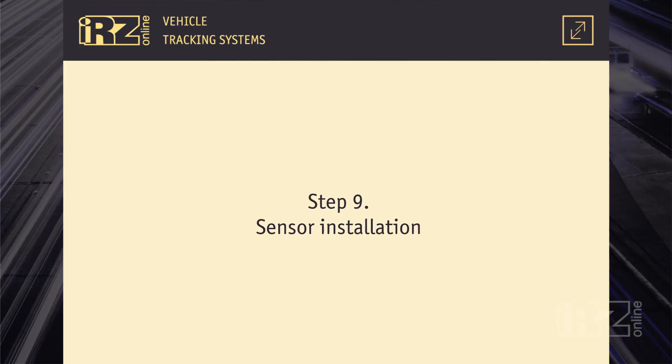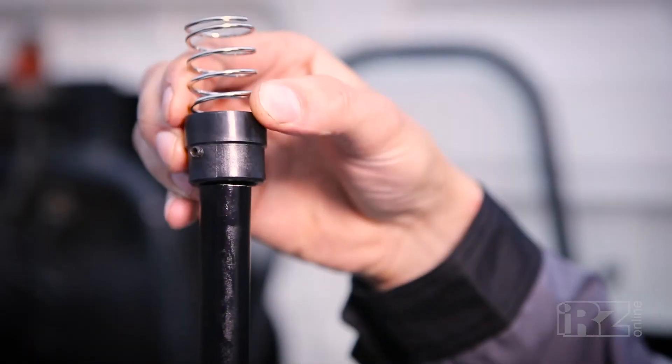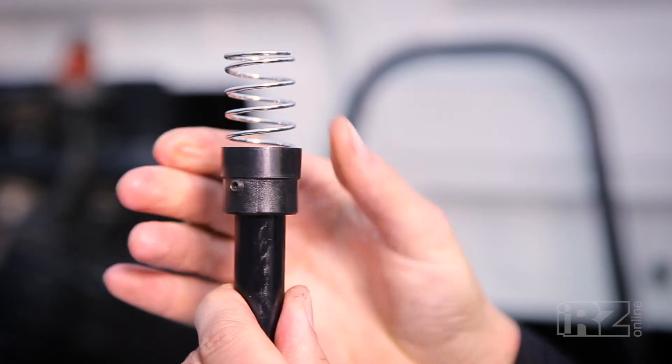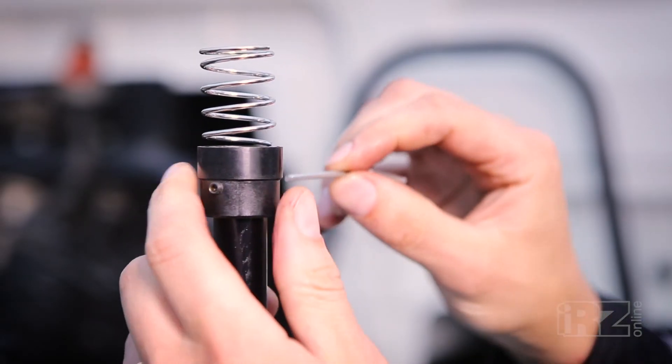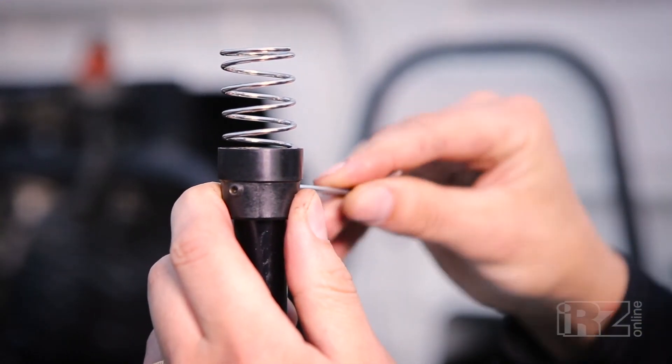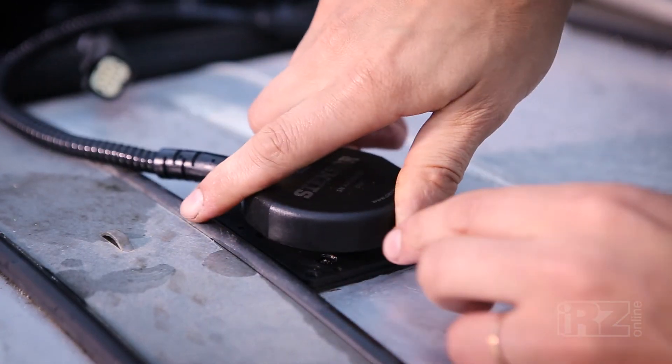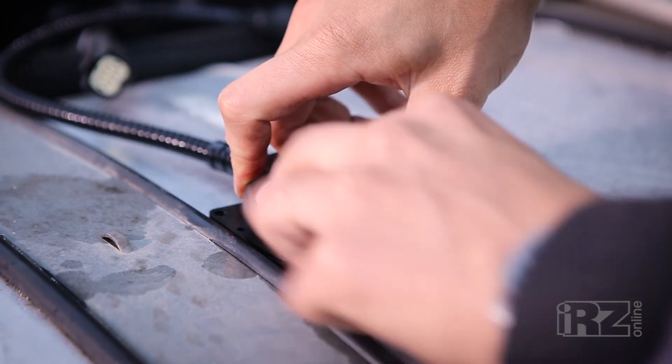Carry out the final sensor installation. Fit the supplied coil spring for the cap on the cut area. Using the Allen key H2.5, spin bolts on the sides of the cap. Set the O-ring. The sensor should be inserted into the hole and turn until it clicks.